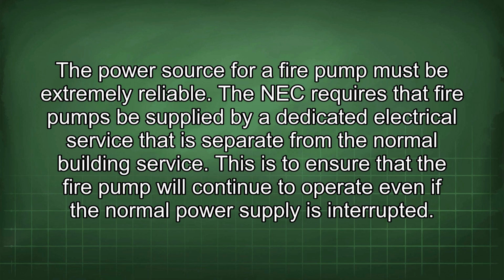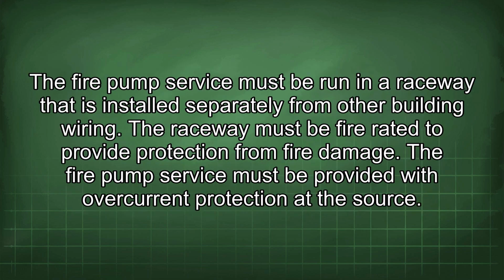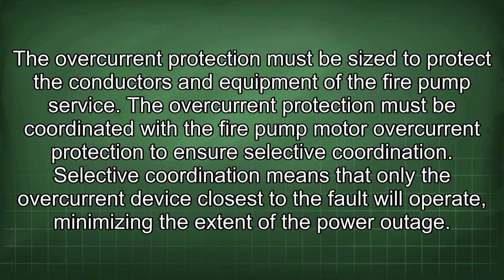The NEC requires that fire pumps be supplied by a dedicated electrical service that is separate from the normal building service. This is to ensure that the fire pump will continue to operate even if the normal power supply is interrupted. Fire pump service must be run in a raceway that is installed separately from other building wiring. The raceway must be fire rated to provide protection from fire damage. The fire pump service must be provided with overcurrent protection at the source. The overcurrent protection must be sized to protect the conductors and equipment of the fire pump service.